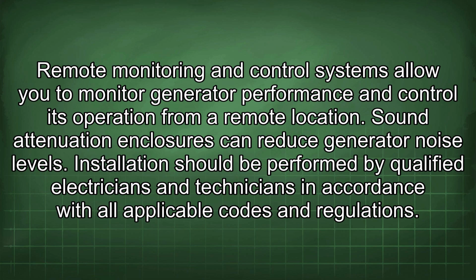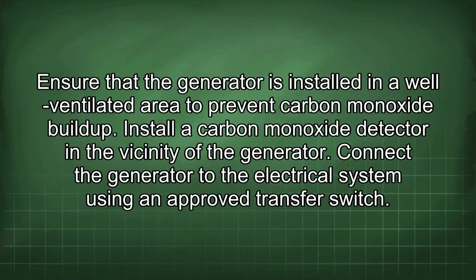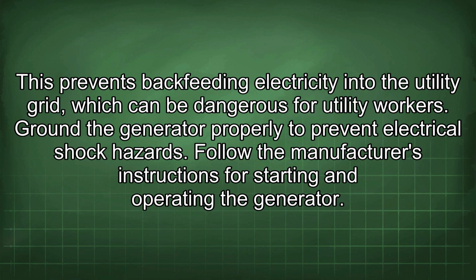Installation should be performed by qualified electricians and technicians in accordance with all applicable codes and regulations. Ensure that the generator is installed in a well-ventilated area to prevent carbon monoxide buildup. Install a carbon monoxide detector in the vicinity of the generator. Connect the generator to the electrical system using an approved transfer switch. This prevents backfeeding electricity into the utility grid, which can be dangerous for utility workers. Ground the generator properly to prevent electrical shock hazards. Follow the manufacturer's instructions for starting and operating the generator.